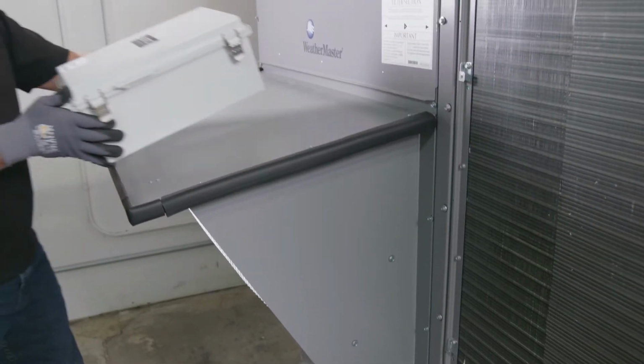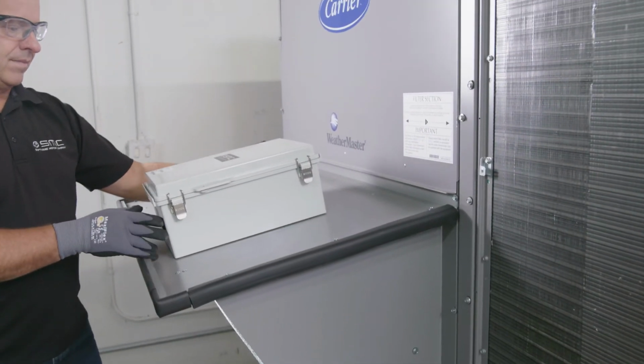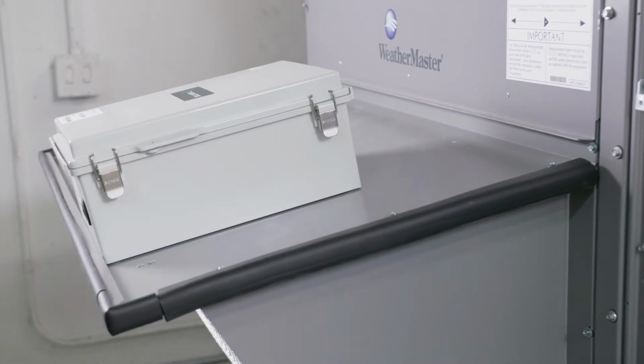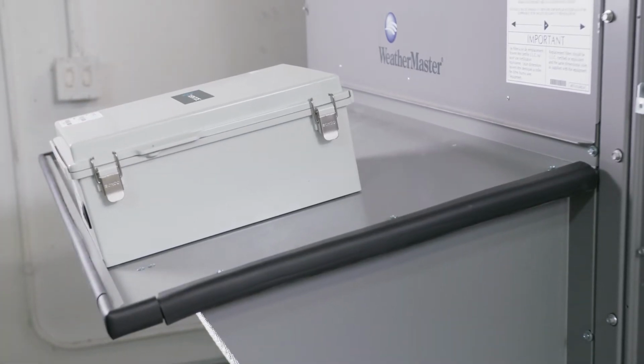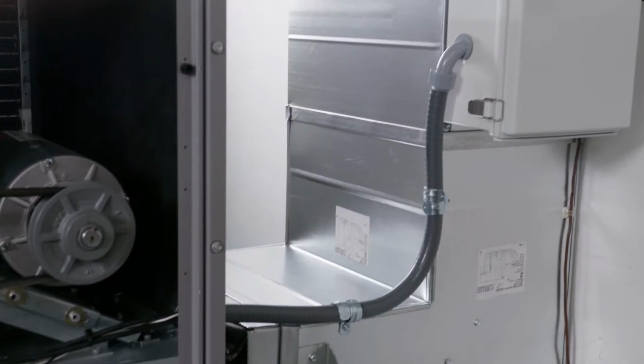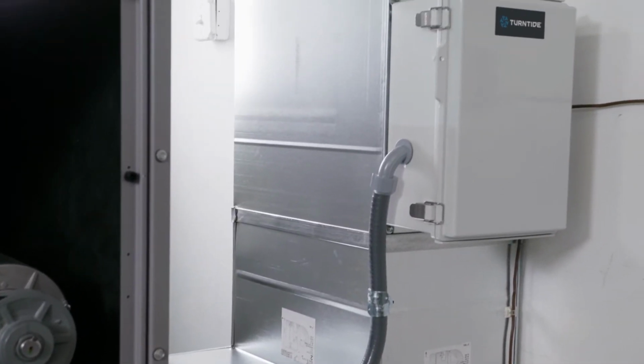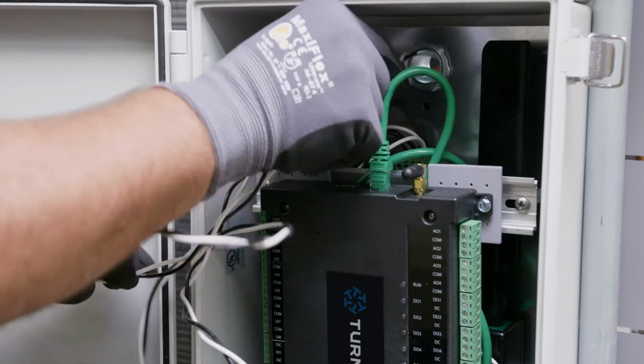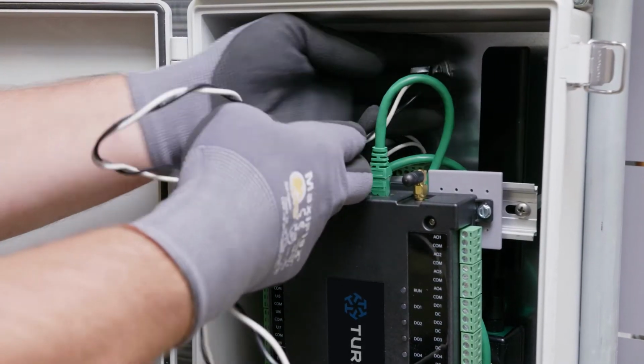If mounting the enclosure next to the main power disconnect or unit control panel is not possible, you can mount it on top of an economizer hood and run the wiring into the control panel. Or if there is not enough room in the unit, you may have to mount it externally and use a seal-tight conduit to connect it to the HVAC unit.